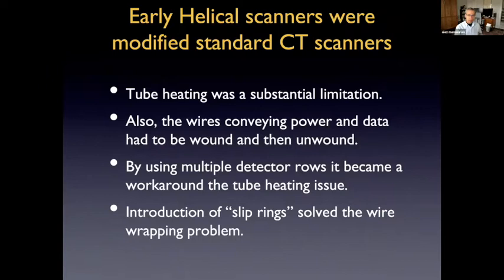So when I say that the big breakthrough was really mathematical, the early helical scanners really were just standard scanners that were just run by putting the table through the scanner while the tube was left on. The problem with those early scanners was tube heating. The tubes were not really designed to be left on. And I can remember in trauma cases, in the middle of a trauma case, trying to stop scanning to allow the tube to cool off. It was a stressful situation.